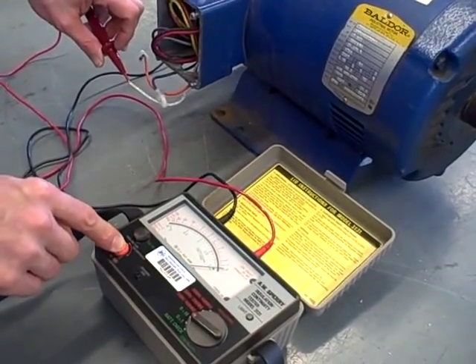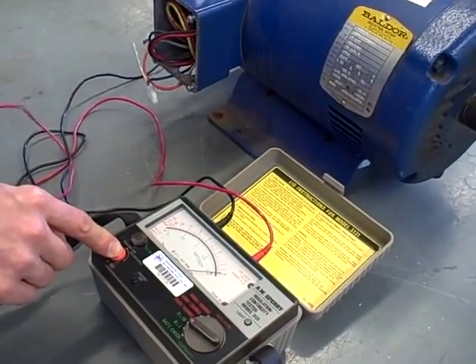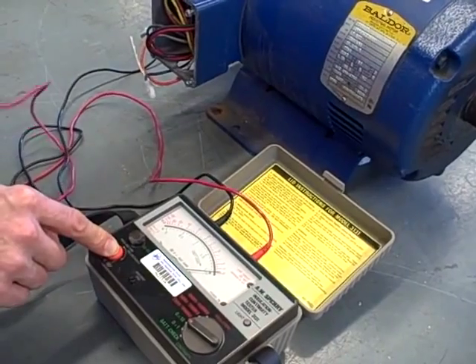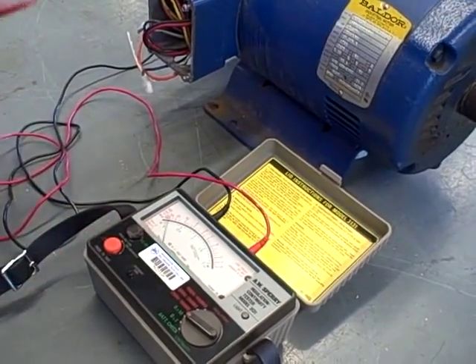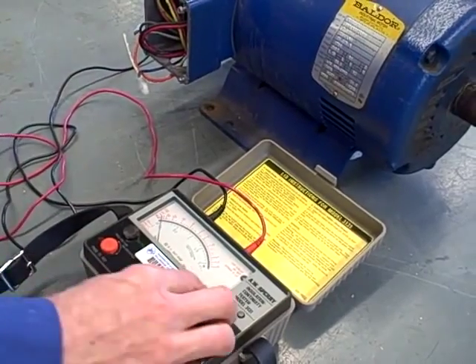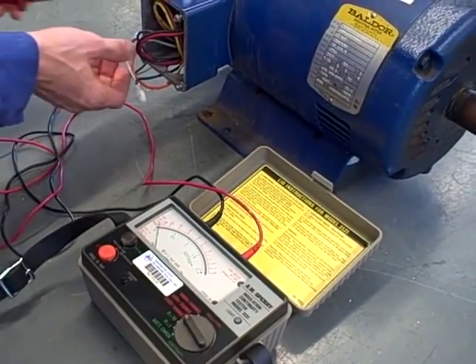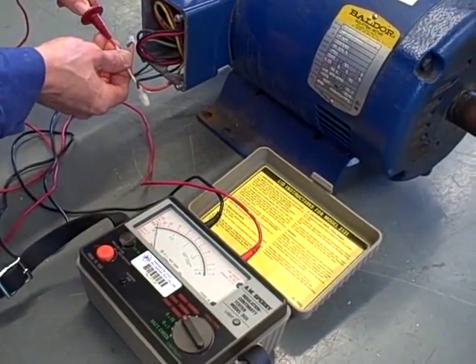Just to prove to you, I'm going to hold this button down and remove the probe. It stays over to the right. It's still reading open. In other words, the ground fault is not being detected on a low voltage mode. The ground fault is only being detected on a high voltage mode.